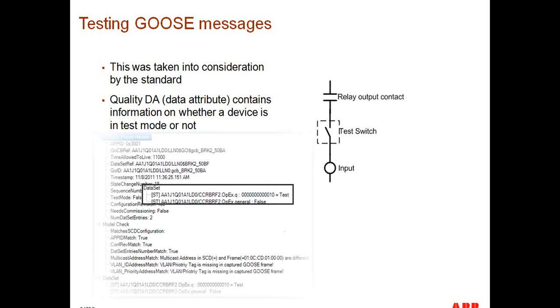So the key here is quality should be transmitted as part of the GOOSE message, and then the quality flag should be used to adjust the behavior of the devices that are subscribed to that particular message, so that they recognize that their peer is being tested.